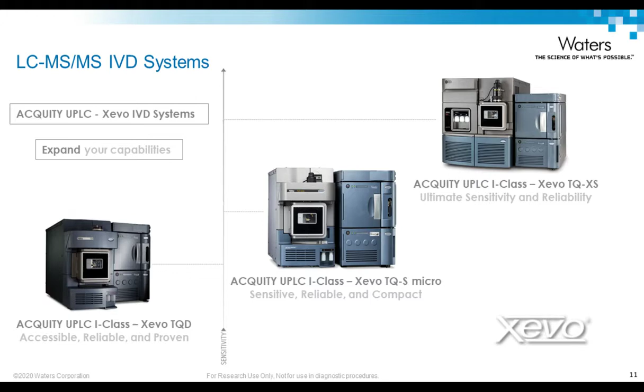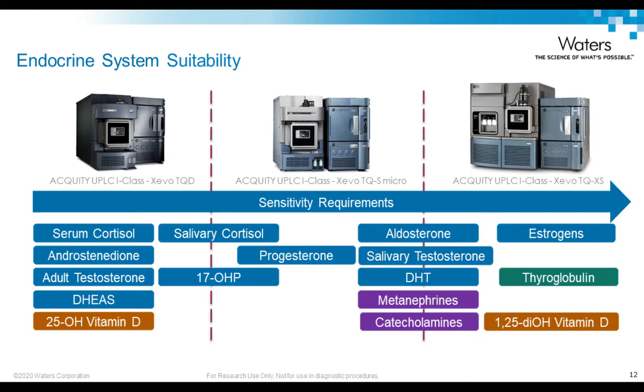This has replaced the Xevo TQS system in the family and is the most analytically sensitive tandem mass spectrometer available. This slide illustrates how we would relate the performance of these IVD systems to the sensitivity requirements of the classes of endocrine analytes. The Xevo TQD system is able to analyze a number of well-characterized analytes such as cortisol, testosterone, and 25-hydroxy vitamin D. The Xevo TQS Micro system is able to analyze these in addition to more challenging analytes such as metanephrines, catecholamines, and aldosterone, which require detection at lower physiological concentrations. The Xevo TQ XS is capable of analyzing all the analytes shown here, including estrogens, thyroglobulin, and the active metabolite 1,25-dihydroxy vitamin D.